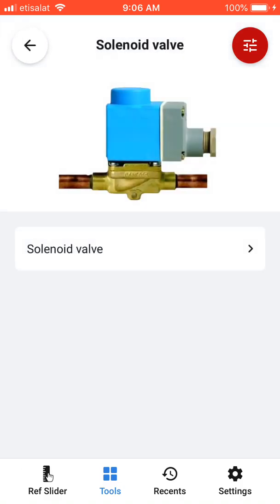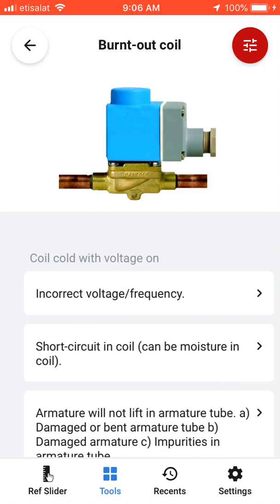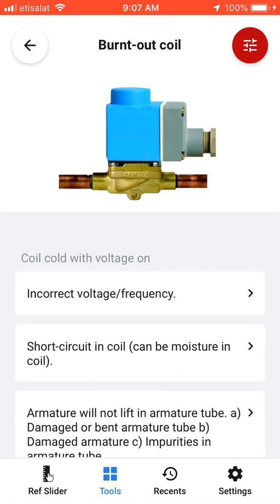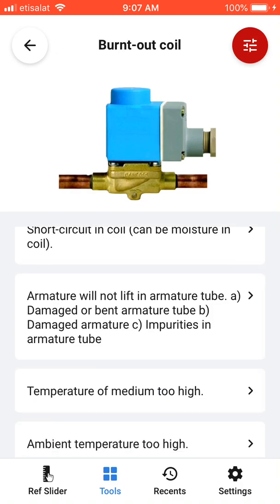You also have the troubleshooter — you can touch any part of the refrigerant cycle. For example, here the solenoid valve: what are the possible troubleshooting issues for this part? One example is a burnt-out coil — this is what you might face, and here is what you do.